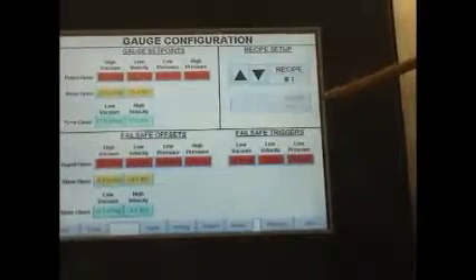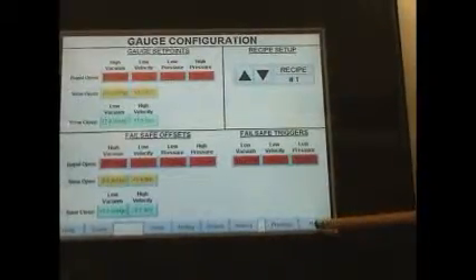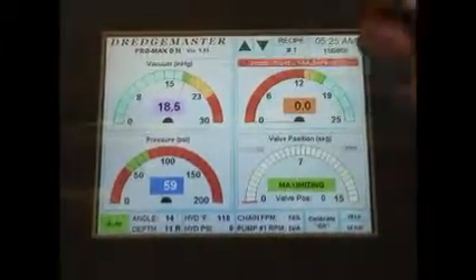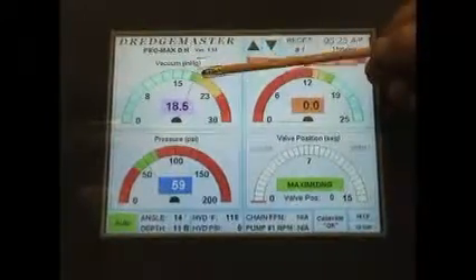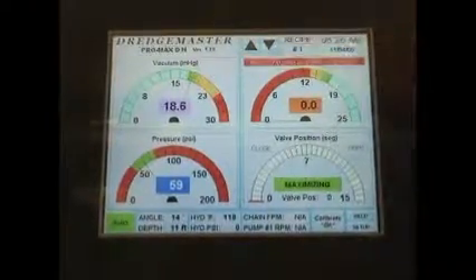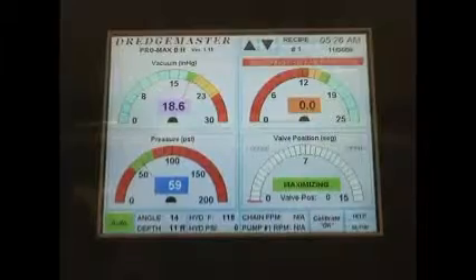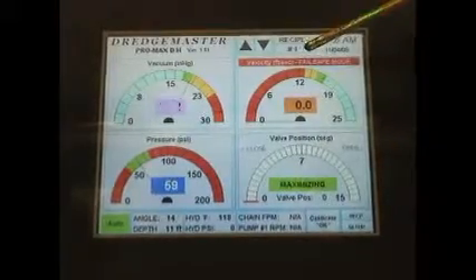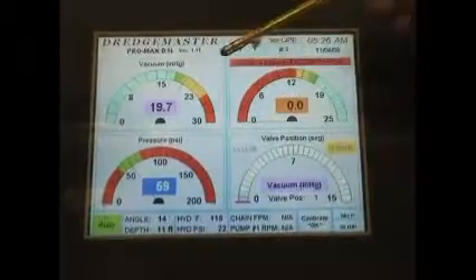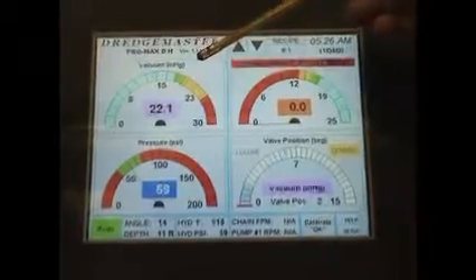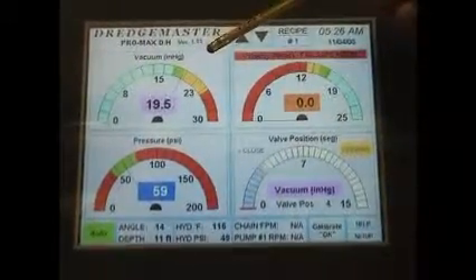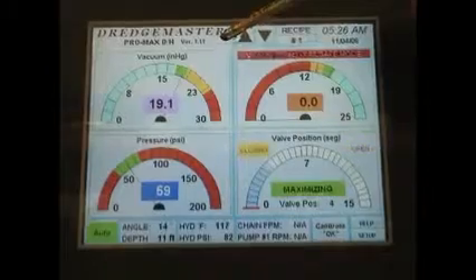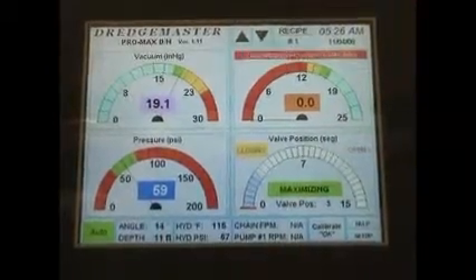Once we made this change, we need to press to accept the new recipe right here, and then we can go back to our main screen and notice how that changes. We have a little nicer green zone area there, but yet, even though our velocity meter has failed, our valve is going to continually work off of whatever the vacuum transducer is asking it to do.